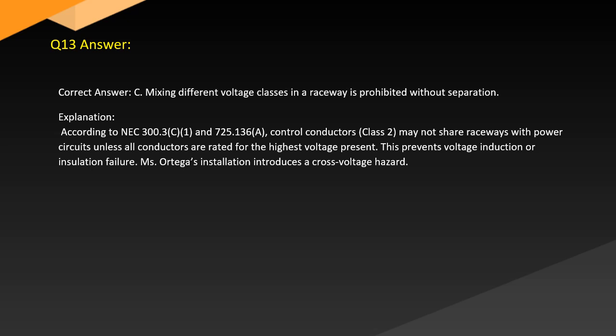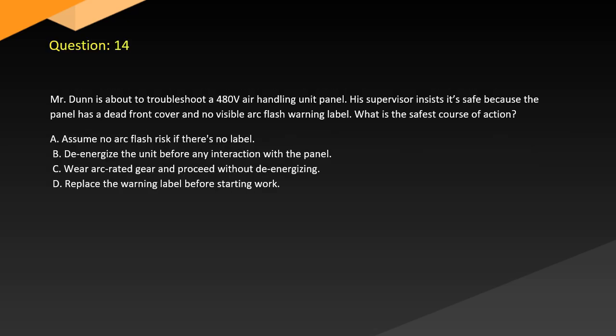Answer. Correct answer: C. Mixing different voltage classes in a raceway is prohibited without separation. Explanation. According to NEC 300.3(C)(1) and 725.136(A), Class 2 control conductors may not share raceways with power circuits unless all conductors are rated for the highest voltage present. This prevents voltage induction or insulation failure. Ms. Ortega's installation introduces a cross-voltage hazard.